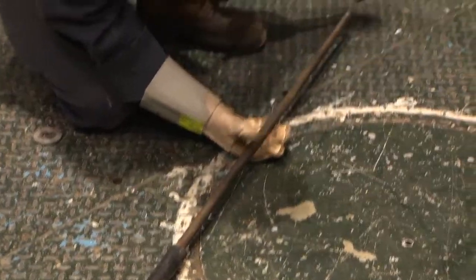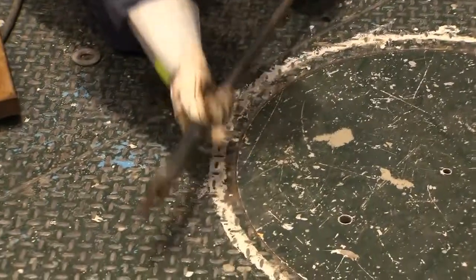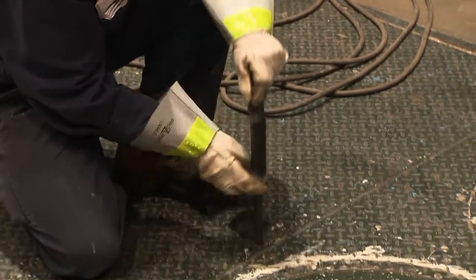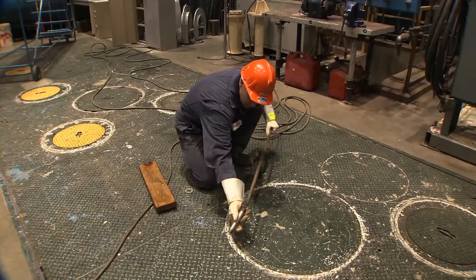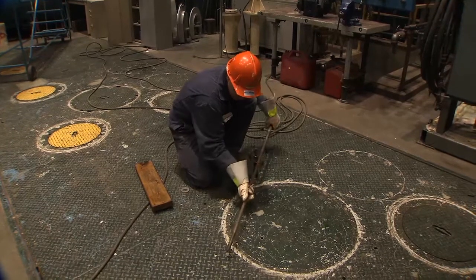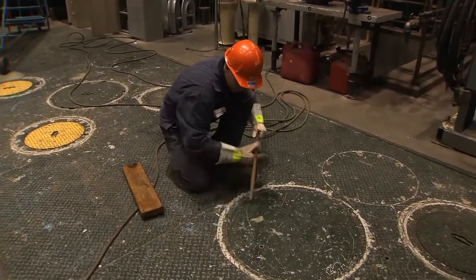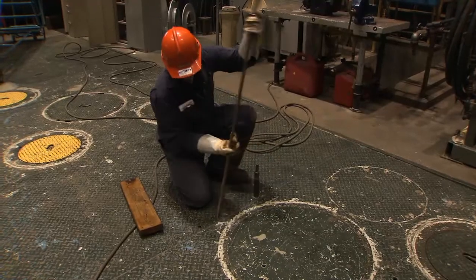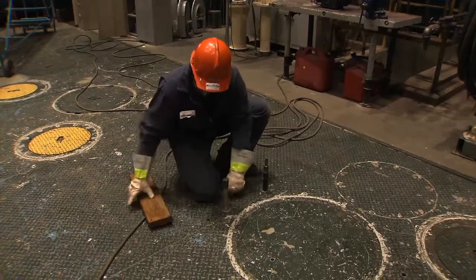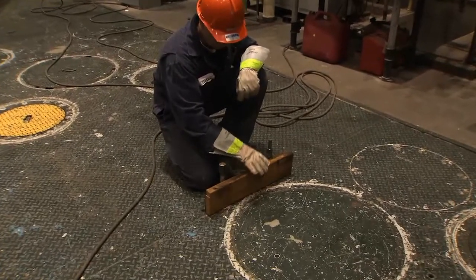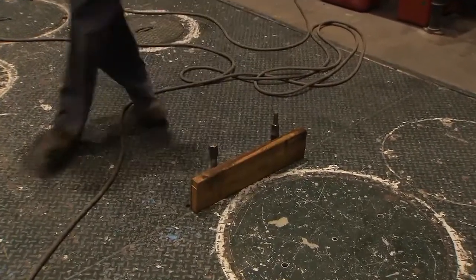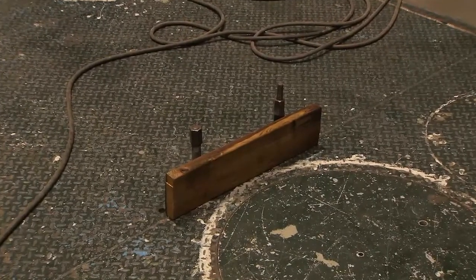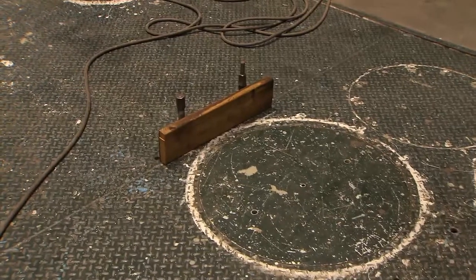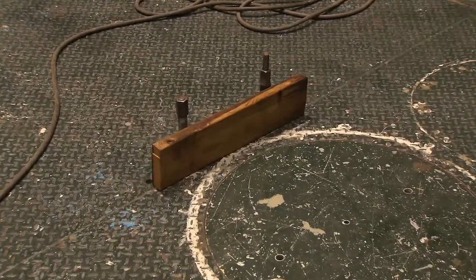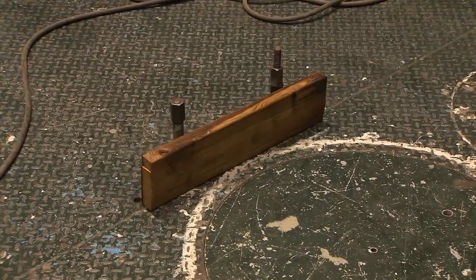Assemble and install 2 metal retaining rods into the 2 slots around the service well in which the bushing will be lowered into. When the rods have been lowered into the holes on one side of the service well, place a thick block of wood between the rods and the edge of the well. The wood acts as a stabilizer to prevent the base of the bushing from any impact with the metal floor around the rim of the well when it's being lowered.